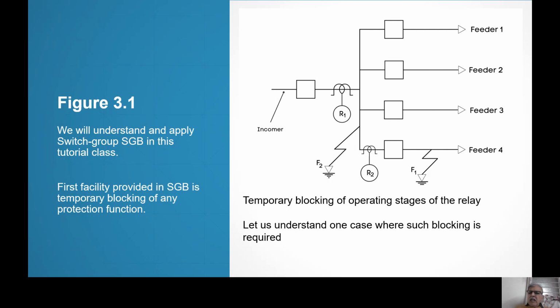Say I have got an incomer which is terminated on a bus and from that bus some 4 or 5 feeders are going. On one of the feeders there is a relay R2, and on incomer there is a relay R1. So you very well know that whenever fault occurs, say at F1, then R2 should operate first. It should isolate the faulty part. But should R2 fail, R1 should give backup.